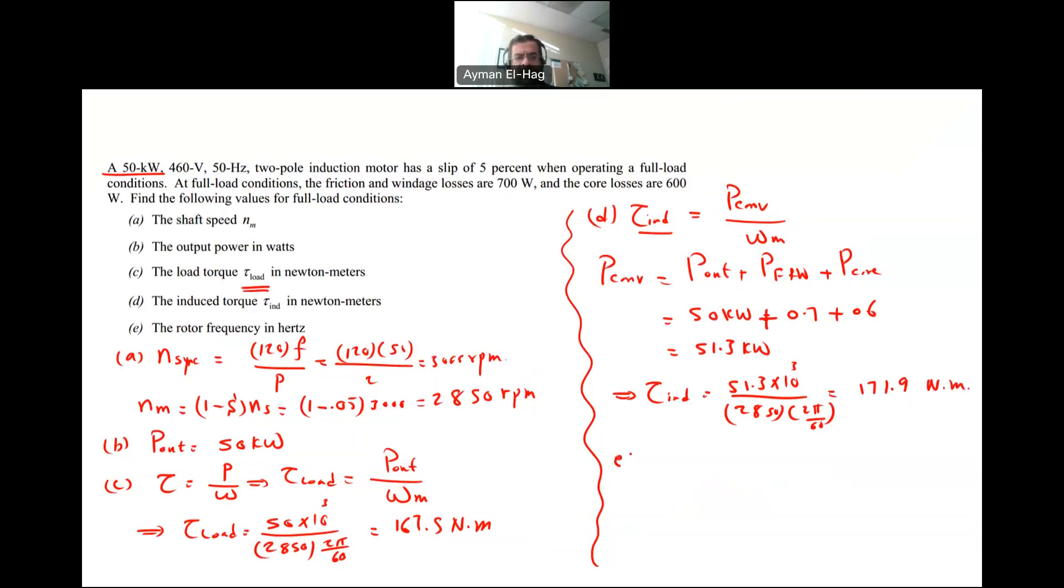The last question is, is to find the rotor frequency. So I want to find the frequency in the rotor is equal to the slip times the frequency in the stator. This is 0.05 times the frequency in the stator, which is 50 hertz. And this will give me 2.5 hertz.